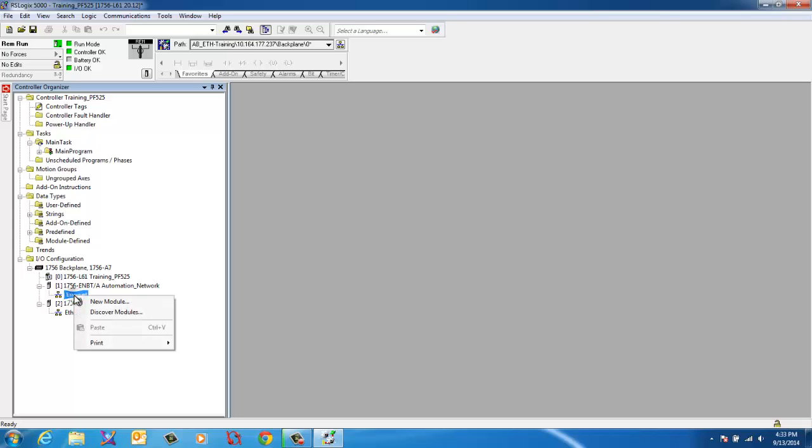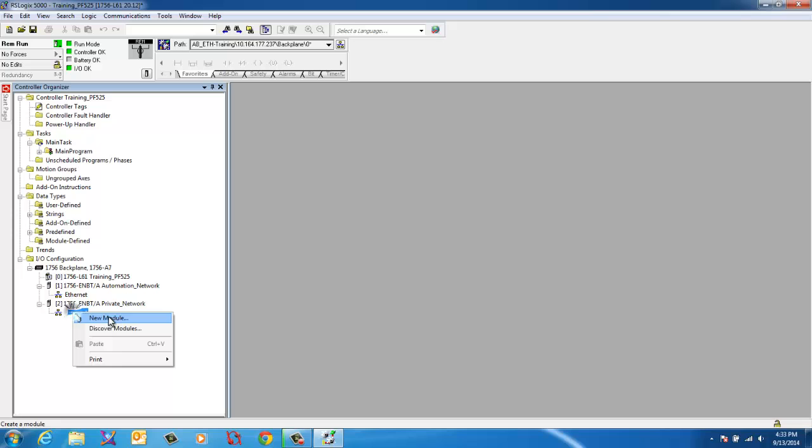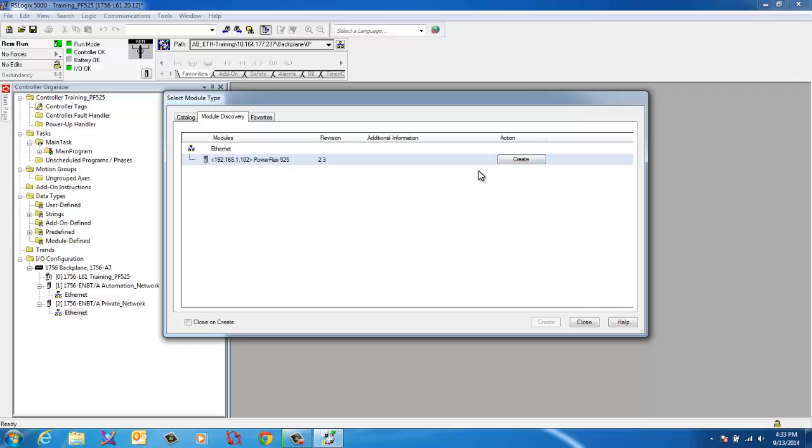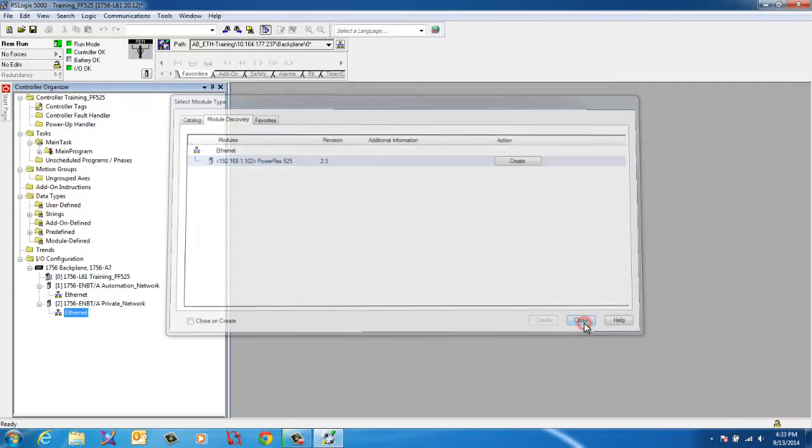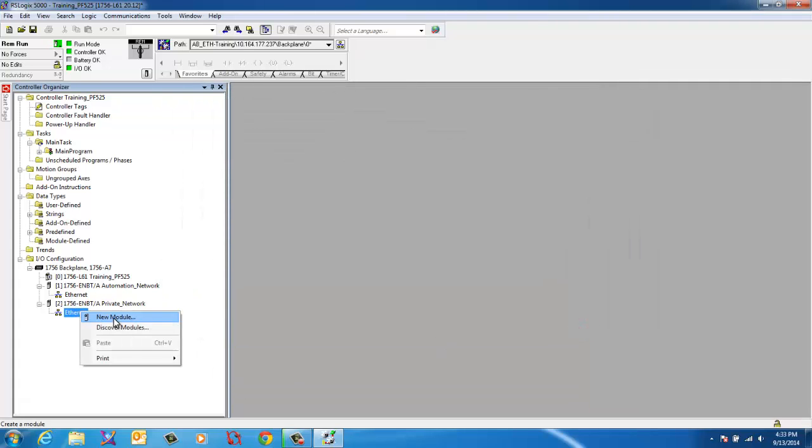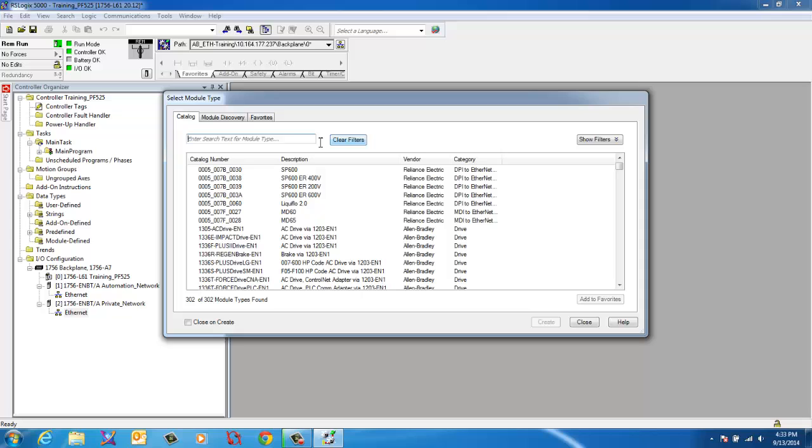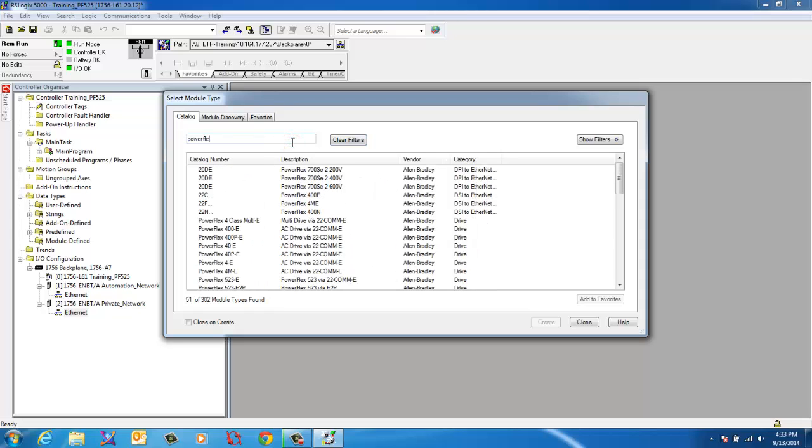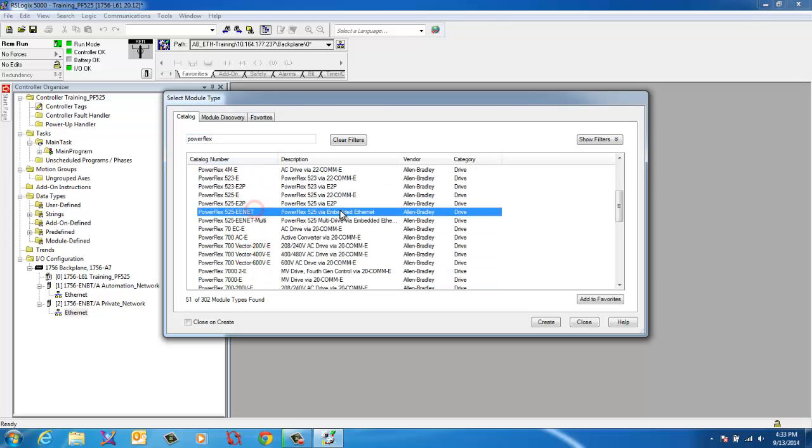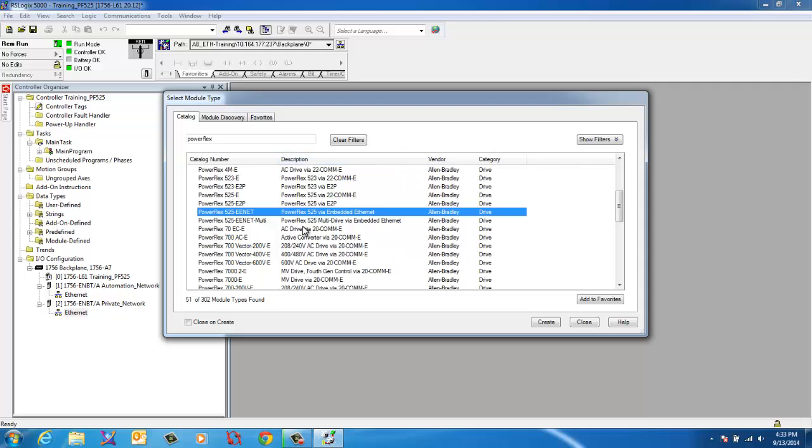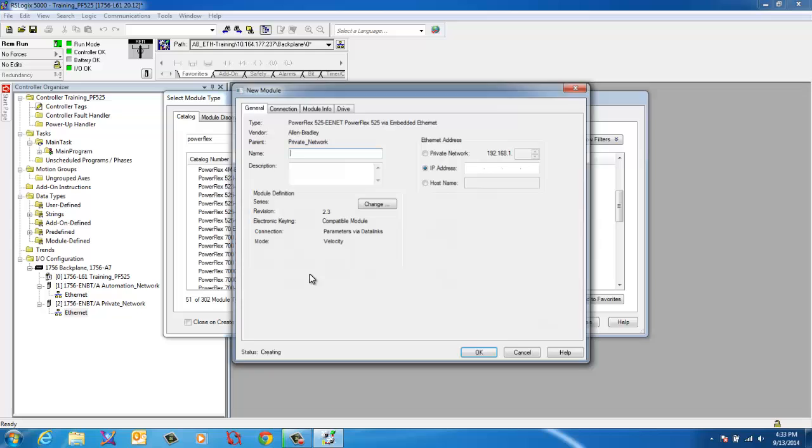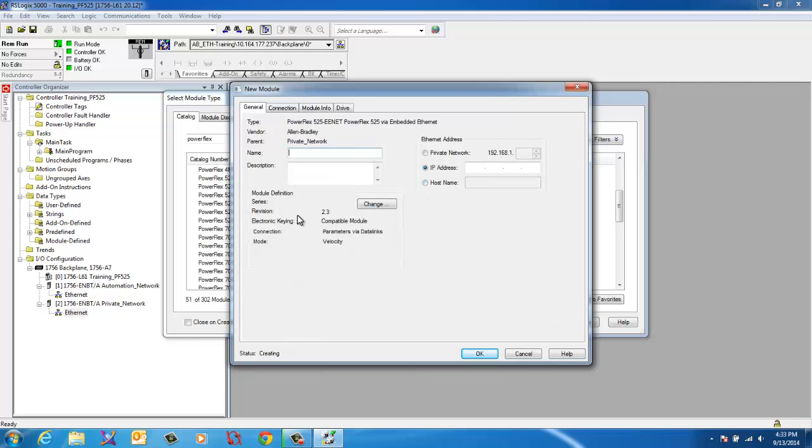So we're going to go over here. We'll do module discovery underneath the private network. There it is. Another way I'm going to show you how to do this and we'll do it the harder way. You can hit create and it will automatically create it with everything that it has with revision 2. But we're going to do it the other way in case you're on older versions that don't support it. We're going to go ahead and right click. We're going to add a new module. It's going to bring up a list. We're going to type in powerflex. And you'll scroll through the list. 525. And we're going to use the one with embedded ethernet. There are different options. You can have dual port. But the one that we're using has the single embedded ethernet port. Which is probably going to be the most typical one. We're going to create it.